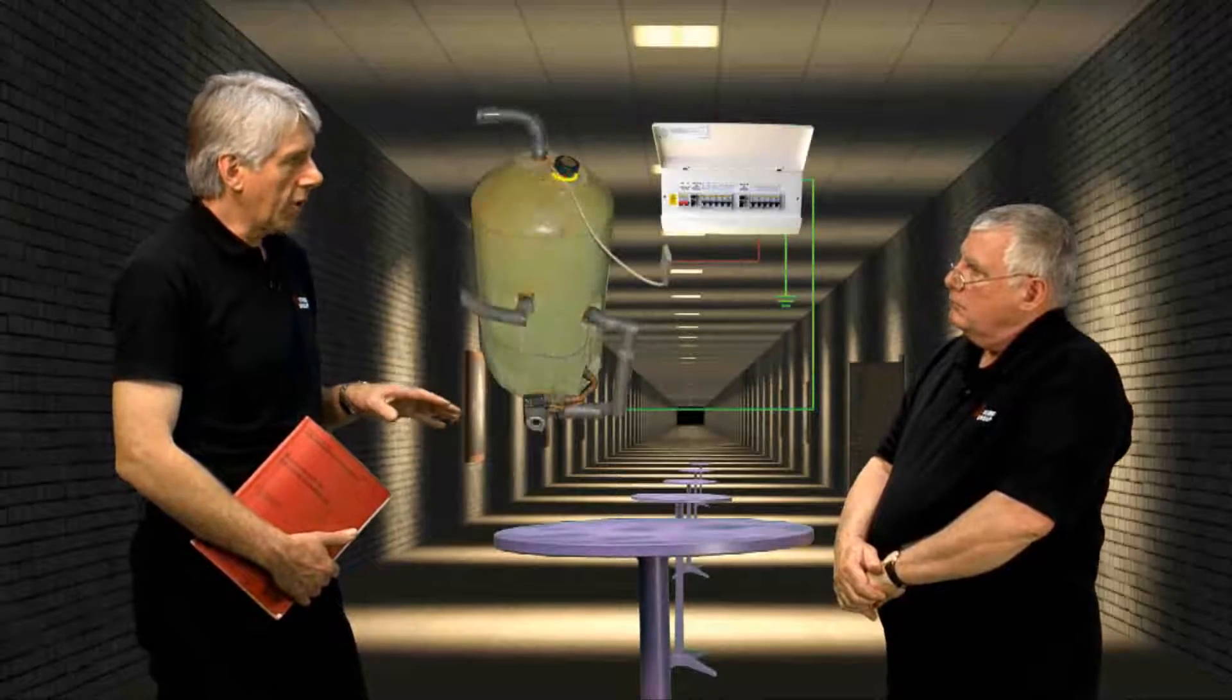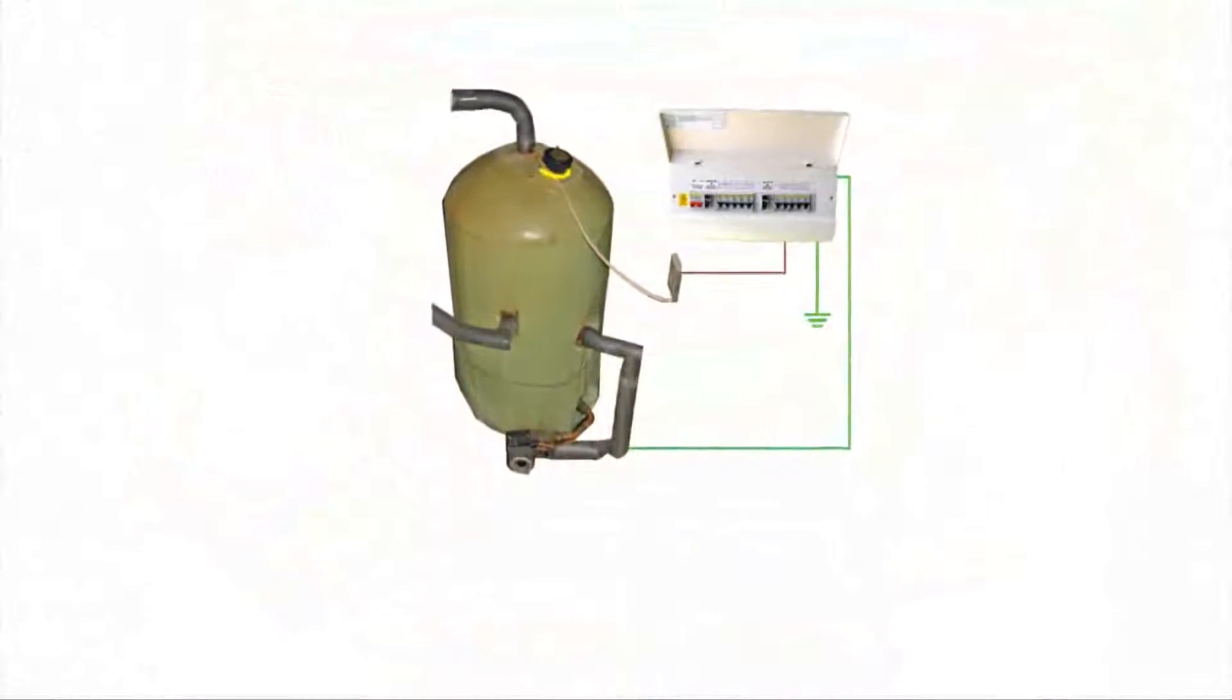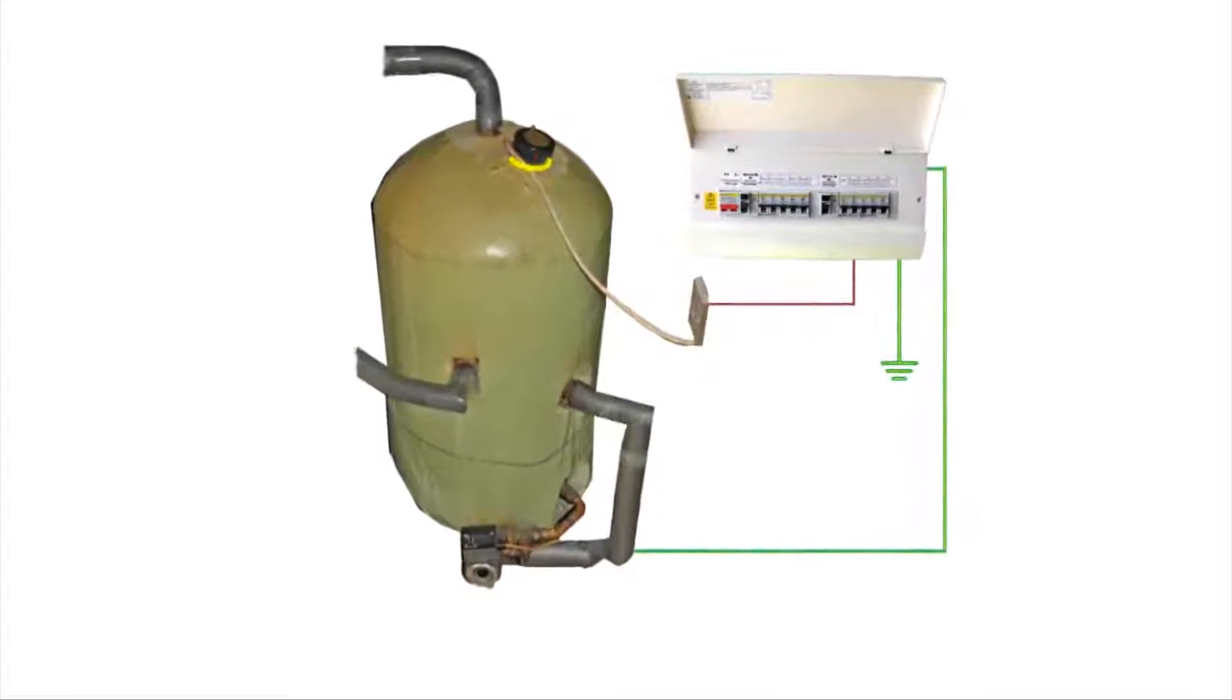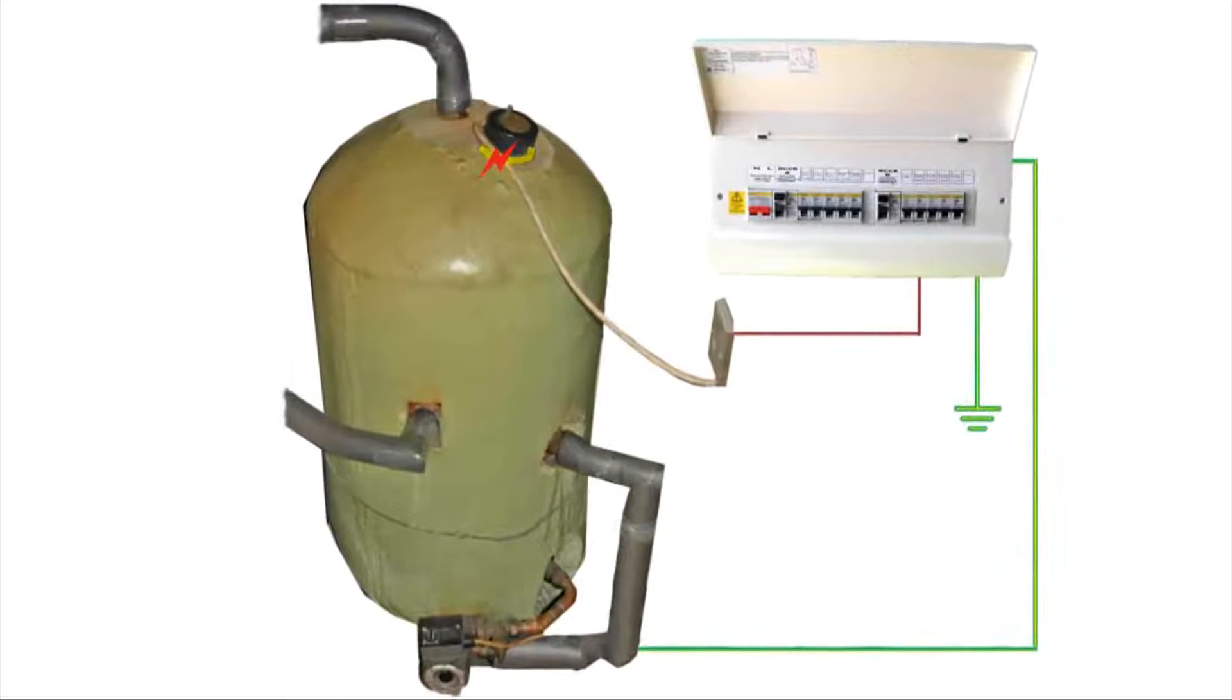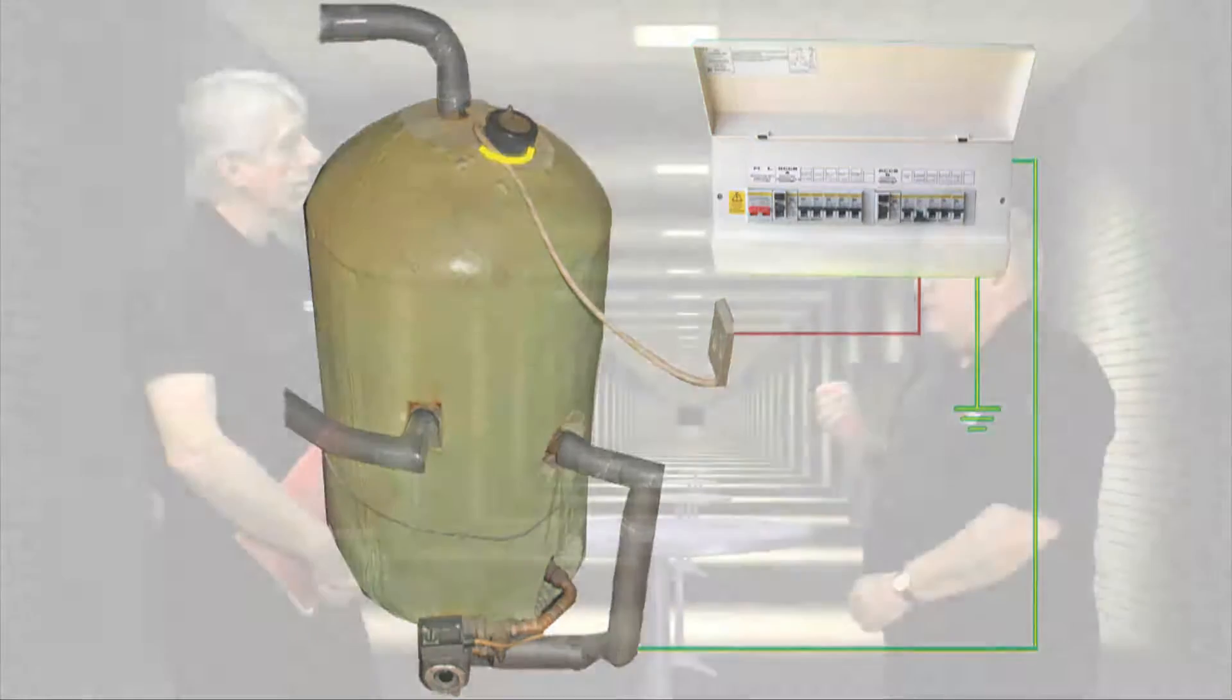Let's imagine the flex on an immersion heater is worn through and the line conductor touches the casing. What actually happens? With effective ADS in place, an earth fault current will flow very quickly to earth, causing the fuse or the circuit breaker to disconnect the circuit within 0.4 seconds. So even if you went to touch it, it will be dead before you did.